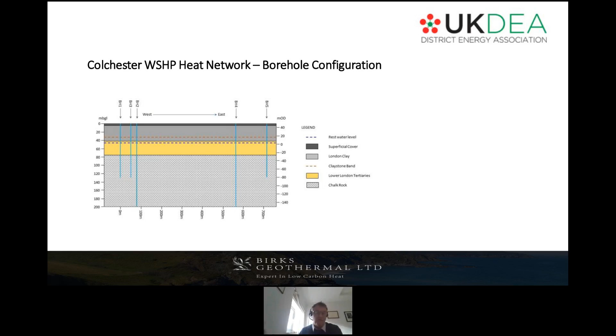These wells have to function to a very high level of performance and have to be very durable. So for the next 25 to 50 years, we're going to be pumping 50 to 60 tons an hour, 7,000 to 8,000 hours a year from these abstraction wells to these re-injection wells. So it's not just a matter of constructing a high quality installation, it's also a matter of maintaining it and looking after it during its working life. And that, in my opinion, has a cost. Well, it does have a cost, and in my opinion, that cost is probably 3 to 4% of the wellfield capex.